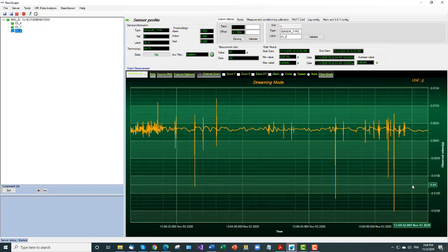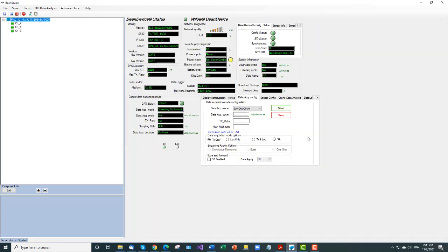But what about the other options where I should enter the data acquisition duration, like in set mode or streaming mode with burst option? In this case, we already choose an automatic number of points, and we said before that the minimum data acquisition duration is 10 seconds. So here you need to enter a duration which is a multiple of 10, means 10, 20, 30 seconds and so on.